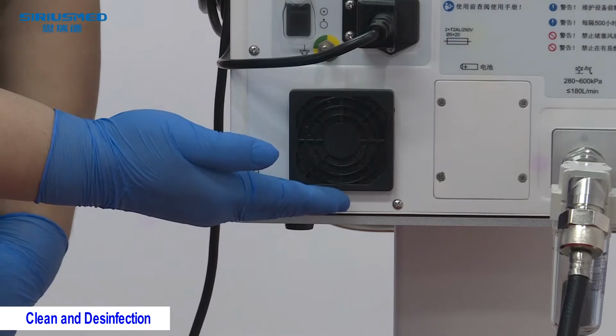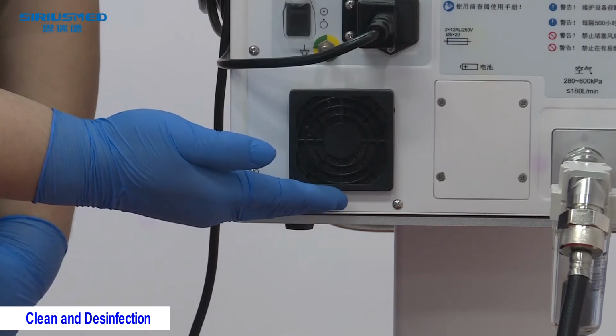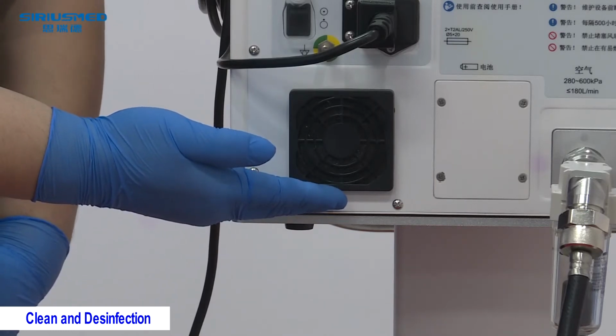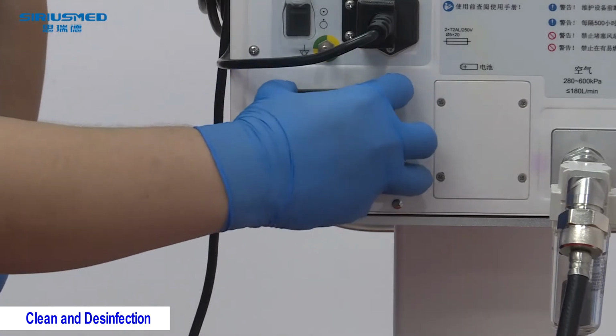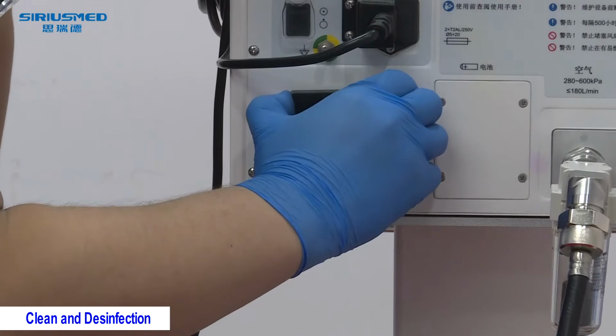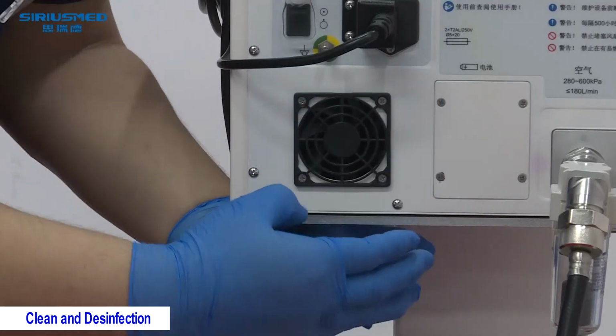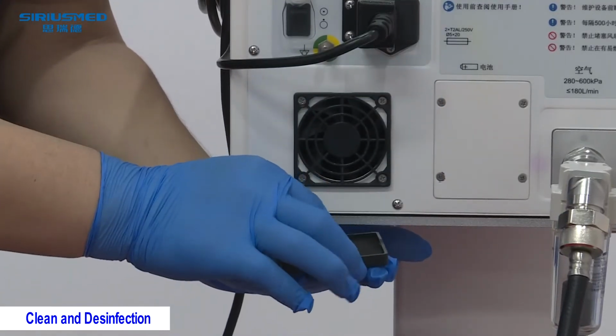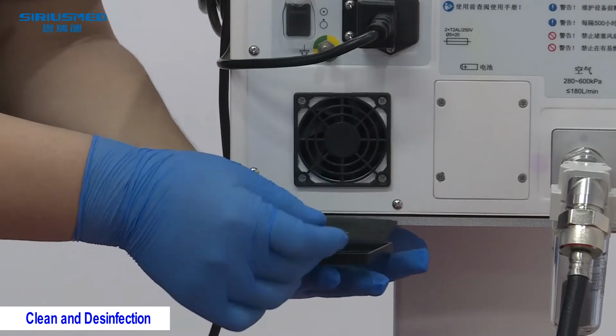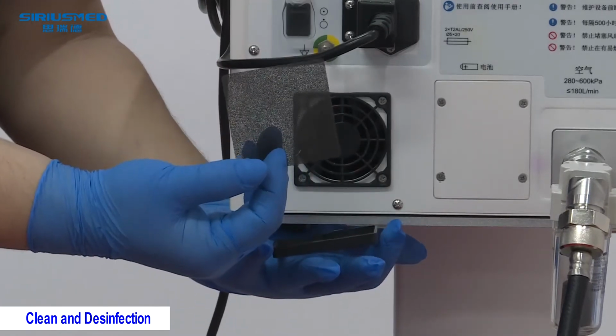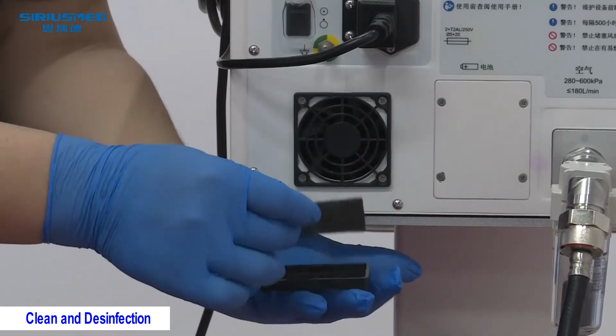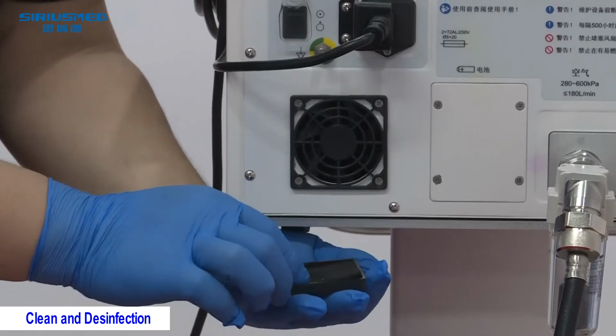Notice of the cooling fan. This cooling fan has a filter inside and needs to be cleaned every 500 hours in the daily use of the ICU room. For this dust filter, you just need to clean it in the water and dry it, then put it back to reset onto the machine.